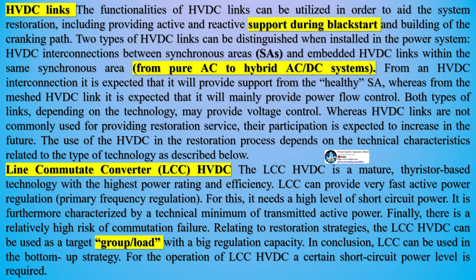as described below. Line Commutated Converter, LCC HVDC. The LCC HVDC is a mature, thyristor-based technology with the highest power rating and efficiency. LCC can provide very fast active power regulation, primary frequency regulation. For this, it needs a high level of short-circuit power. It is furthermore characterized by a technical minimum of transmitted active power. Finally, there is a relatively high risk of commutation failure.